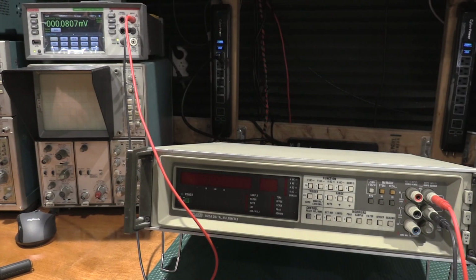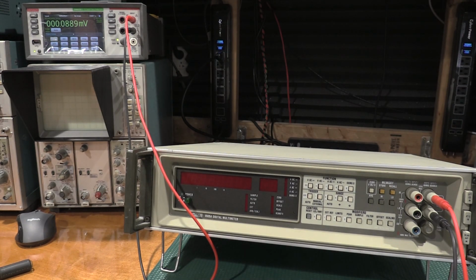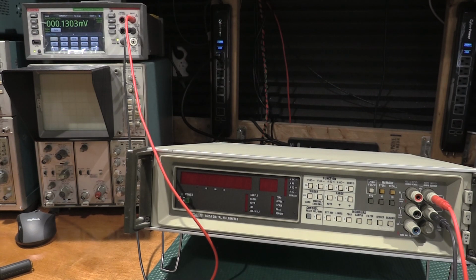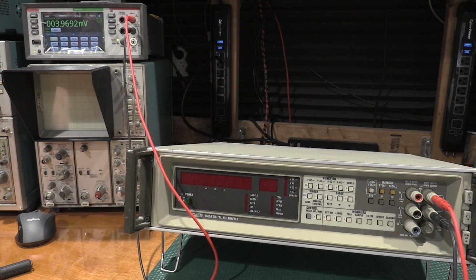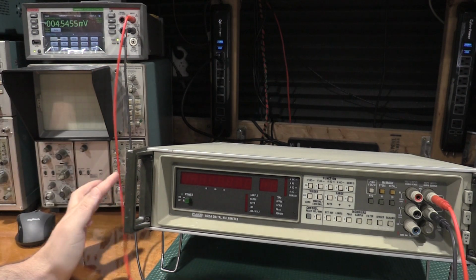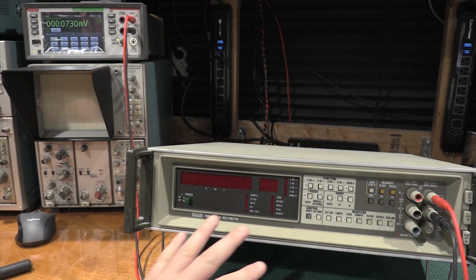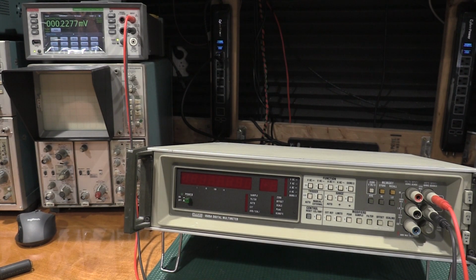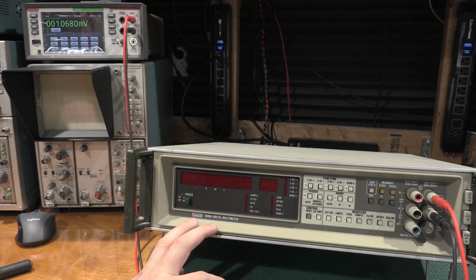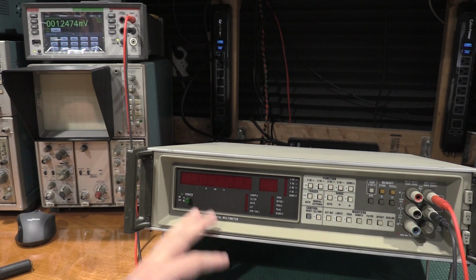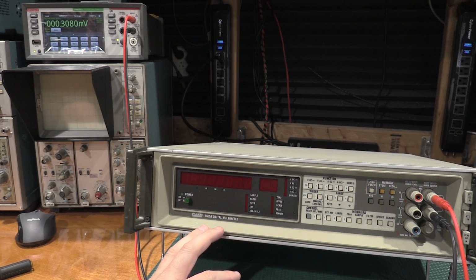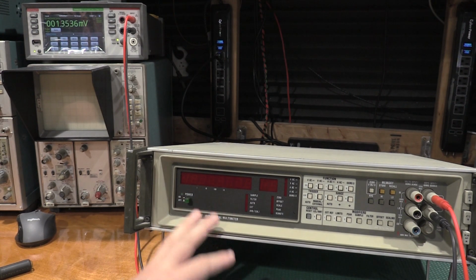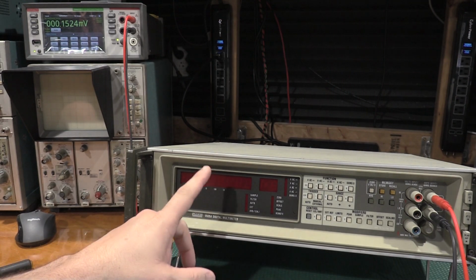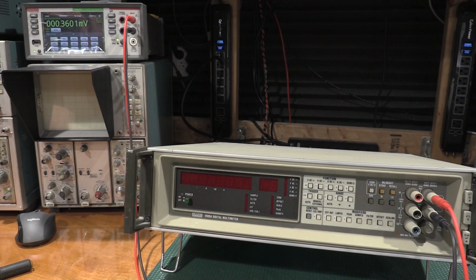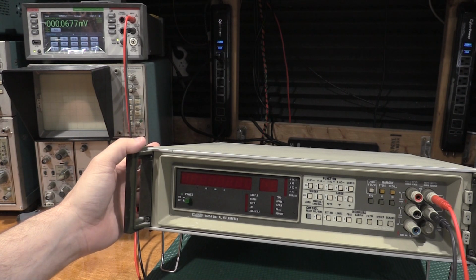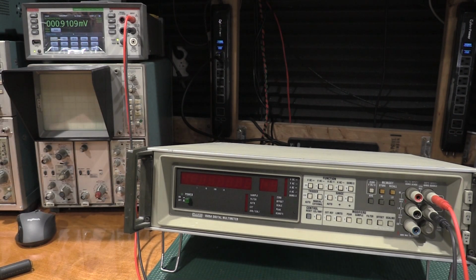Okay, to test if a meter is good for doing high voltage measurements and voltage divider probes, we're looking for a meter input of 10 megohms. So I got my Fluke 8505. This is one of the older meters I have in the lab, but it still has some uses on the AC range. This is the best spec on the AC range for all the meters in the lab for high frequency. Not necessarily accuracy or anything like that, but if I remember correctly, this thing will measure up to 10 megahertz, which is pretty high for a bench DMM.